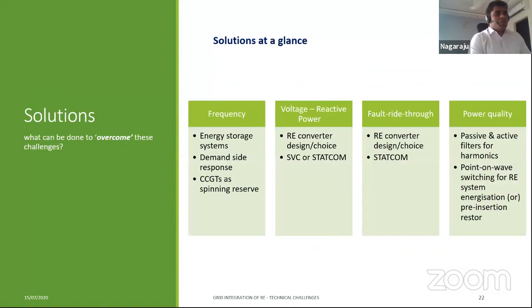Okay, so solutions at a glance. Again, I have four parts: frequency, voltage, then operational issues such as fault ride through, and power quality. For frequency, as the issue is on the source side in power injection into the grid, one of the latest, state-of-the-art solutions is to use energy storage systems to support the renewable energy to provide the required frequency support. Energy storage is coming up quite heavily, and I worked on it recently as well. It is seen as one of the major solutions to this problem.